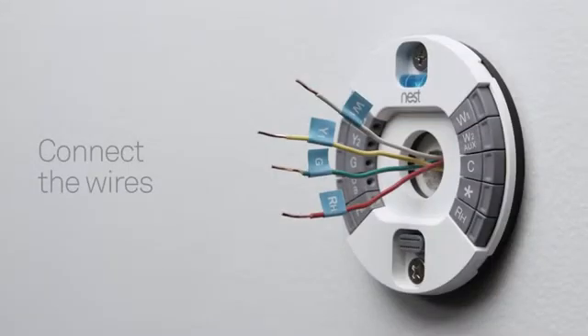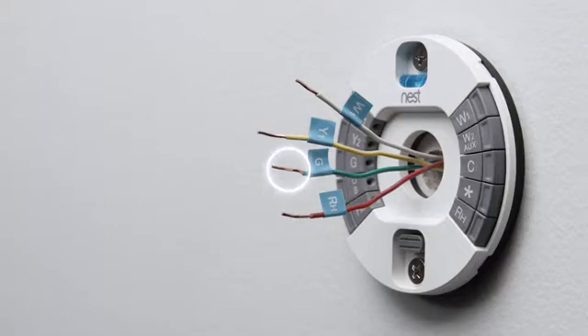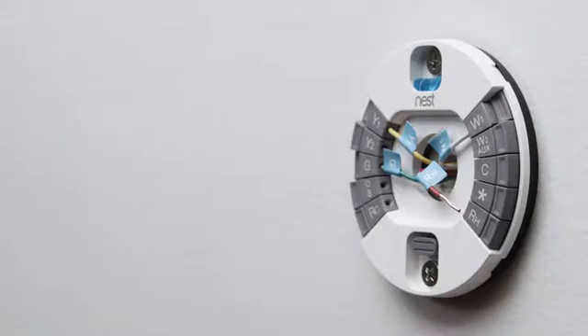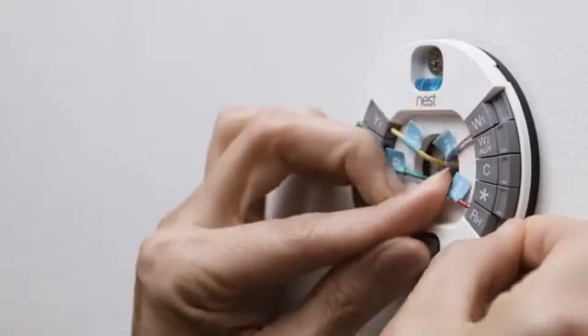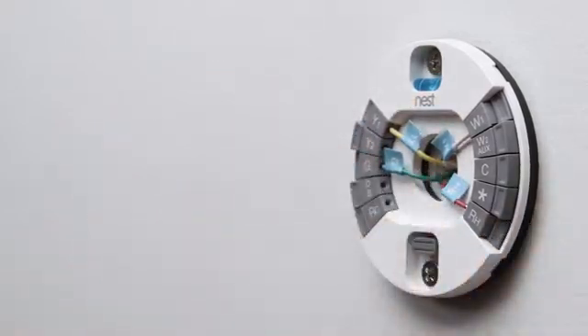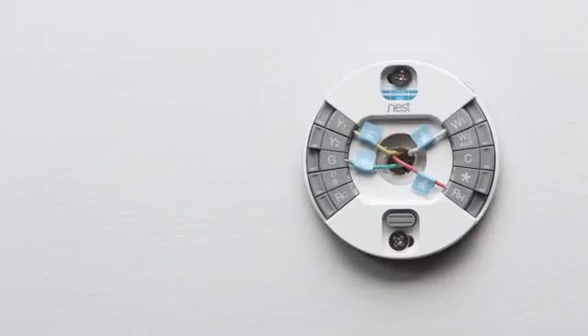Now it's time to connect the wires. Check the ends of your thermostat wires. They should be straight. If not, restrip them and trim the ends, leaving three-eighths of an inch or ten millimeters of wire exposed. Insert each wire that has a label into the matching connector. Simply hold down the connector button and push the wire all the way in. Make sure that the connector buttons stay down after you've inserted each wire. Otherwise, your Nest thermostat may not get enough power and you won't be able to finish setup. Only put one wire into each connector, and don't connect any wires to your Nest thermostat that weren't connected to your old thermostat.